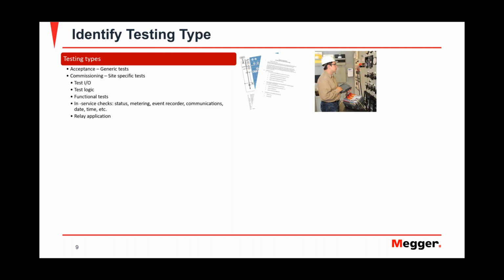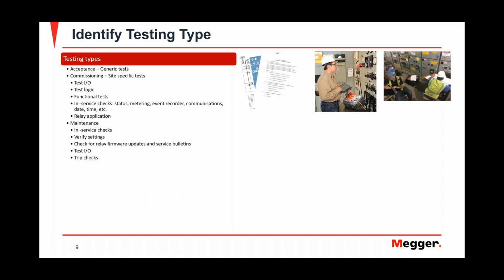This is a more stringent test. And the most important thing is you're testing the application of the protection, the application of the relay, not only the relay itself. Then you could do maintenance tests, which have to do more with in-service checks. This is a relay that's already installed, and you're verifying that there hasn't been any changes on the settings. You could update the firmware on this or in the relays itself. If there is any service bulletins, you shut down the machines, and then you could do all your maintenance checks.